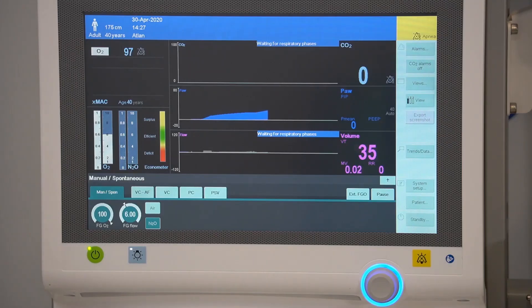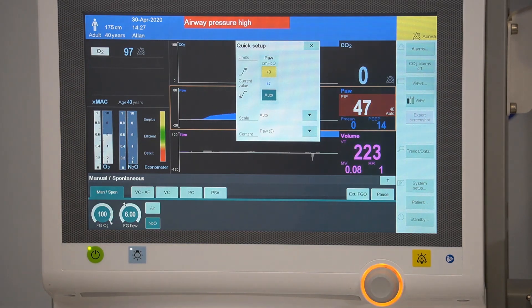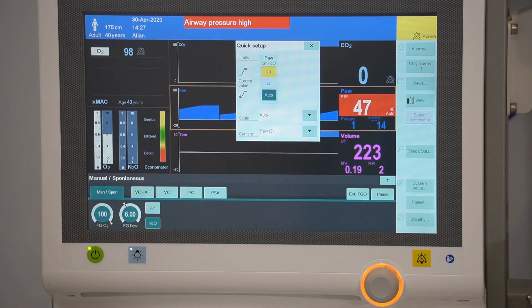Alarms are colour coded and assigned to three priority classes depending on their urgency. Messages with the highest priority are red in colour, this requires immediate attention. The message will be highlighted in red and you'll also hear a repetitive tone.